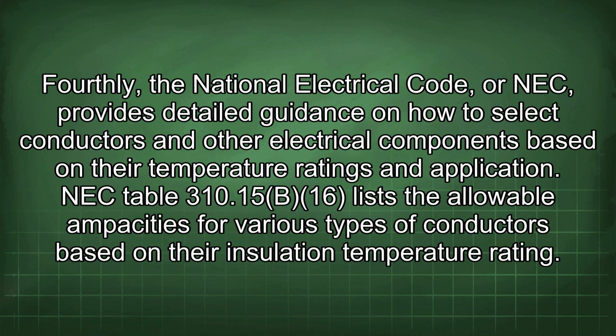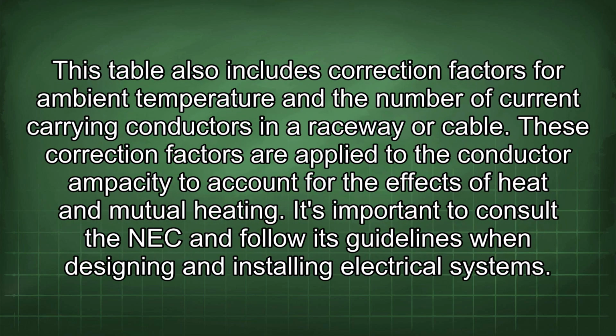Fourthly, the National Electrical Code, or NEC, provides detailed guidance on how to select conductors and other electrical components based on their temperature ratings and application. NEC Table 310.15(B)(16) lists the allowable ampacities for various types of conductors based on their insulation temperature rating. This table also includes correction factors for ambient temperature and the number of current carrying conductors in a raceway or cable.